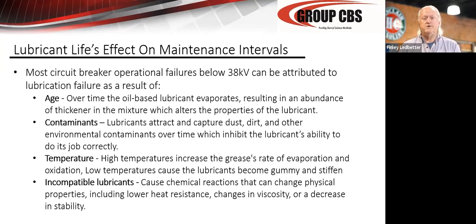High temperature is a problem to grease. Varying temperature is a problem to your breaker, so you have to consider temperature. Incompatible lubricants is one of the biggest problems. That's not true. The biggest problem is people doing maintenance on the breaker that damage your breaker, that don't know what they're doing. The next biggest problem would be incompatible lubricants or a lack of lubricant.